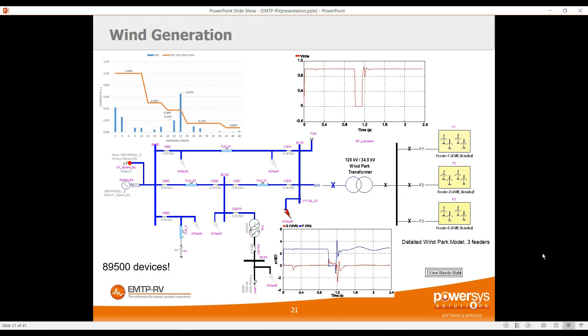EMTP is increasingly used for wind generation studies. A common study is power quality: the wind park is modeled as a harmonic current source injecting harmonics from order zero up to order 50 or higher. During the simulation, the wind park injects these harmonics and we monitor the voltage at the bus. Using scope view, we display the harmonic level for each order and compare with a standard such as IEEE 519. In this example, harmonic number 22 exceeds the standard limit, meaning a filter must be added.